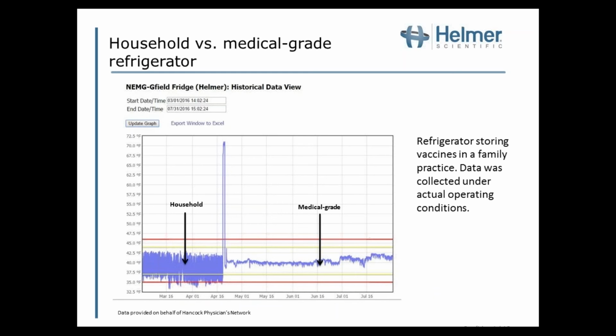Here's some real-life data from both a household and a medical-grade unit. The red lines represent the CDC recommended range — since this is older data, they use 35 as the lower end. You can see the household unit on the left fluctuated too much to keep vaccines in range, with multiple excursions over about a one-month period. Likely all of those vaccines would have needed a manufacturer check, and many would not have actually been good. On the right, the medical-grade refrigerator kept a tight range — within just a few degrees Fahrenheit over a period of months.